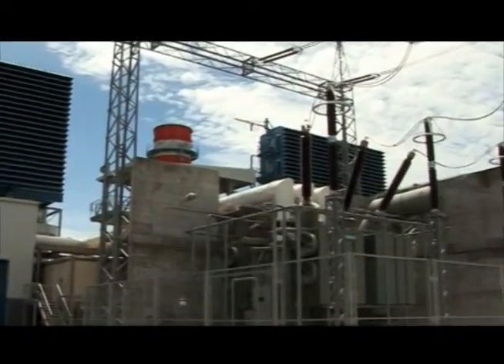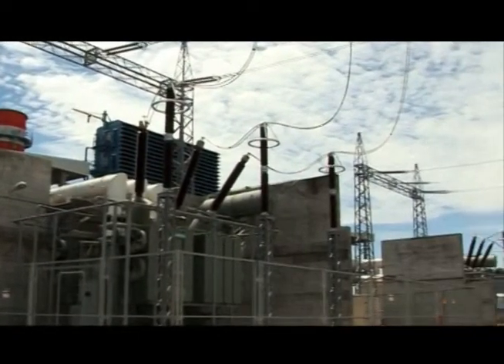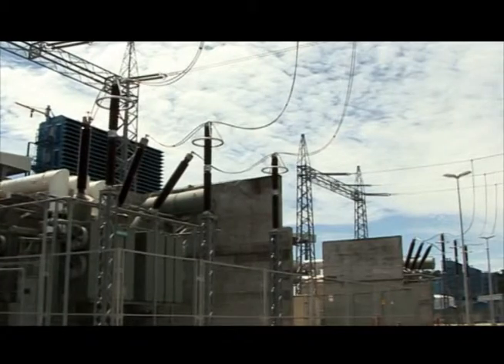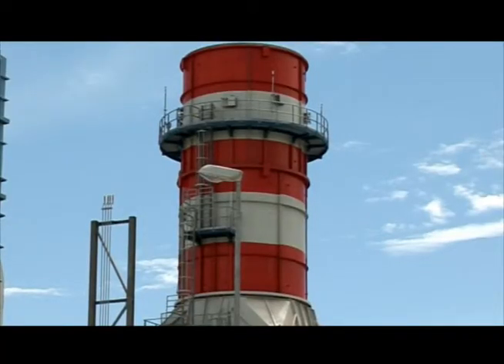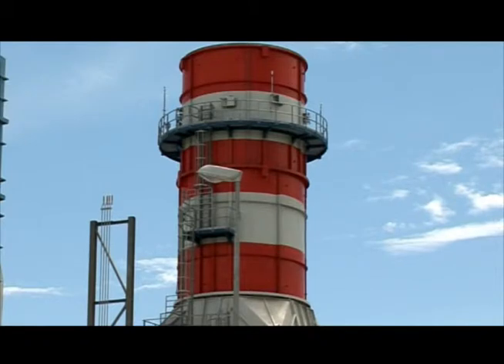There is a switchyard here currently evacuating the outputs of the gas turbine generators to the national grid at 330 kV voltage level, connecting lines from Benin City and Ikeja West substations by means of a link to one of the two circuits of the Benin-Ikeja West transmission line.